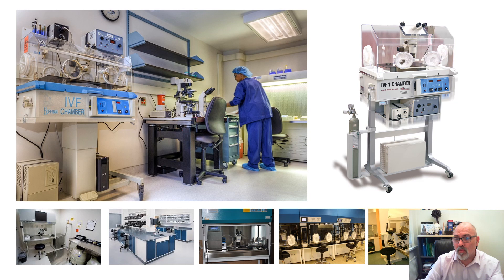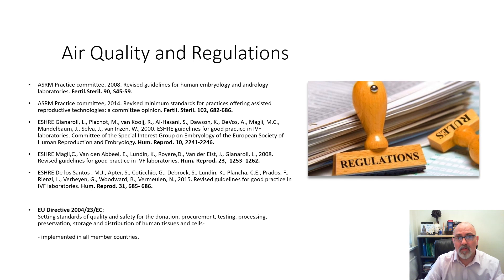High levels of VOCs were found to accumulate in incubators — the very place we don't want them. Boone in 1999 demonstrated that controlling air quality in an ART laboratory was beneficial to fertilization and embryo development. This led to inline filters for medical gases, standalone units to clean air, handheld particle monitors and VOC counters as part of quality management. Various ingenious ways to create protected environments include isolators and laminar flow hoods, though societal guidelines on specifics remain vague.